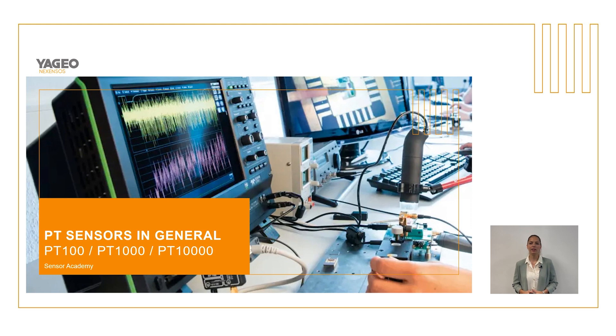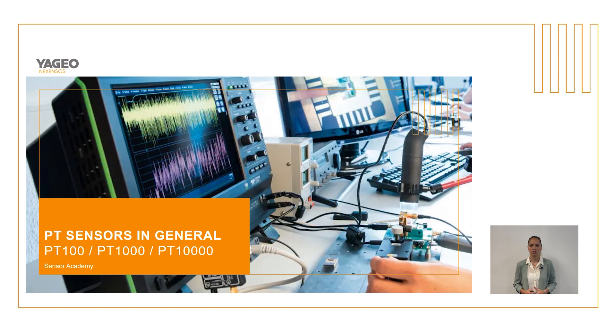In the specification of our sensors, we indicate the nominal resistance at zero degrees Celsius. Accordingly, a PT100 has a resistance of 100 ohms at zero degrees Celsius, and a PT1000 has a resistance of 1000 ohms at zero degrees Celsius. We offer a PT100 and a PT1000 as standard products.